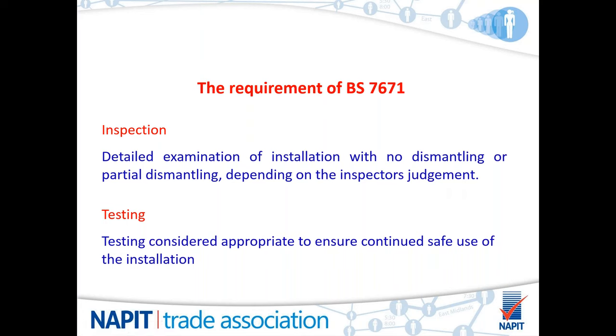BS 7671 asks for inspection and testing. Inspection is the main part of the process. Testing is done to back up that inspection process. Guidance Note 3 asks for a detailed examination of the installation with no dismantling or partial dismantling. The more that people take to pieces, the more faults they're liable to put back onto the installation when they start to reinstate. It's the inspector's judgment as to how far they need to go to get the judgment that they need to find. The testing is done in a considered appropriate manner.